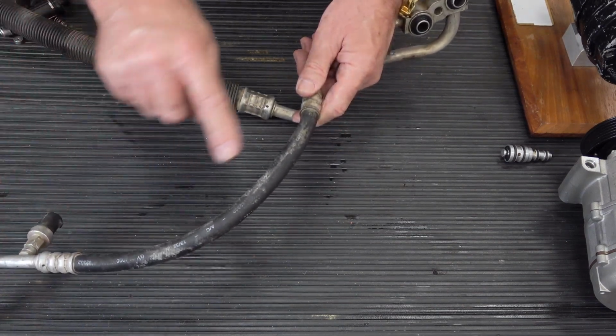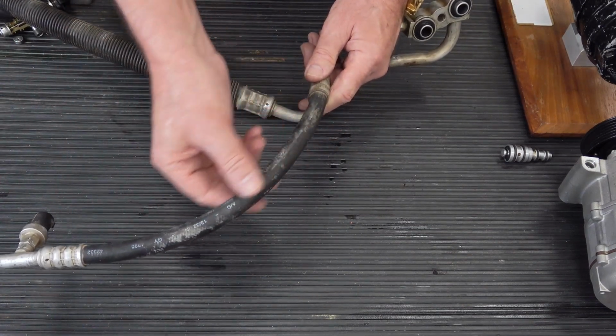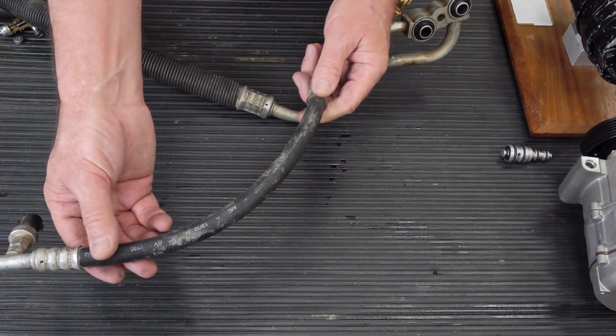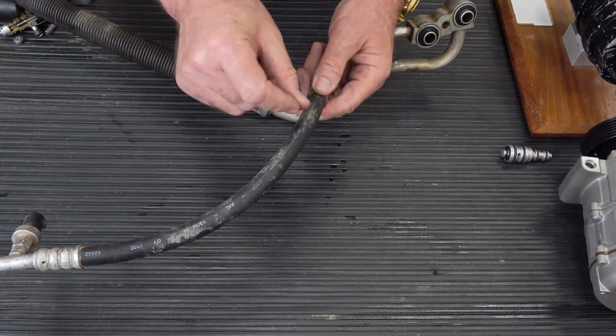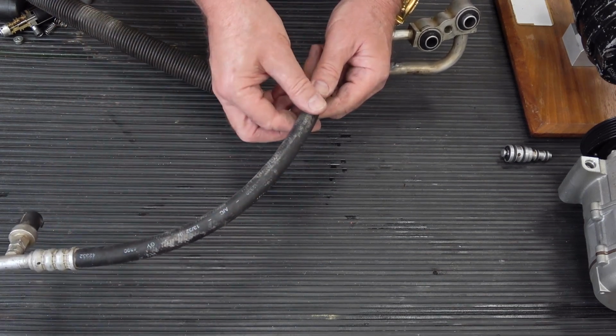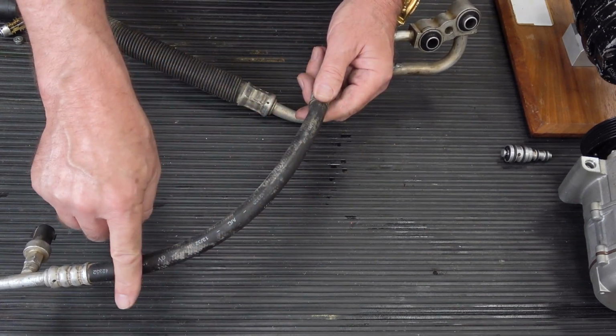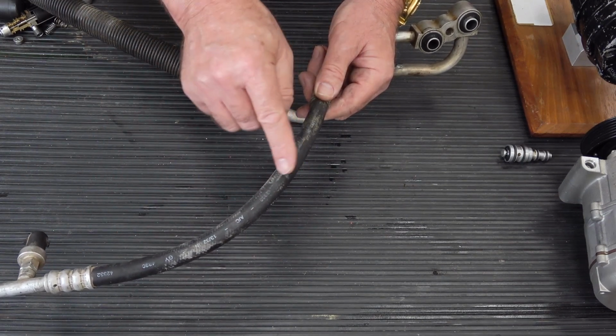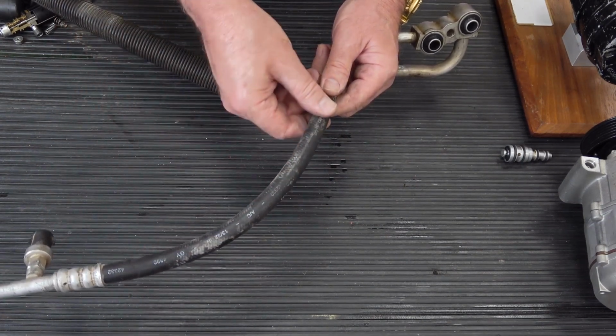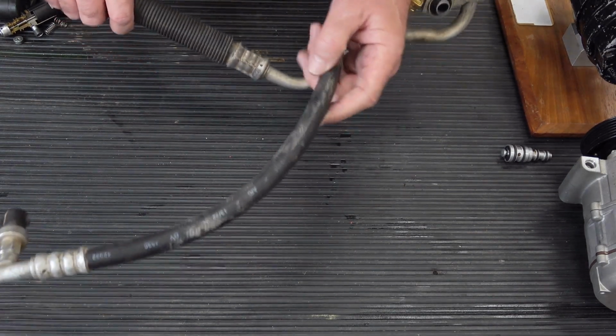Another problem with hoses as they get older is the barrier can become permeable, so the whole entire surface area of the hose can leak or weep. And the leak is so diffuse, so minute at any one point, that you might not even ever pick up the leak with a conventional electronic leak detector. So again, another reason to at least consider, I'm not saying that you should, but you should at least consider replacing hose assemblies.